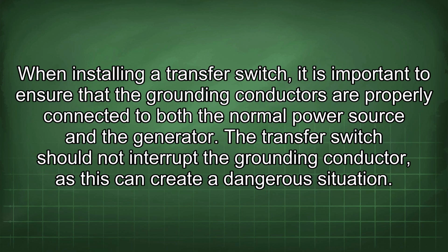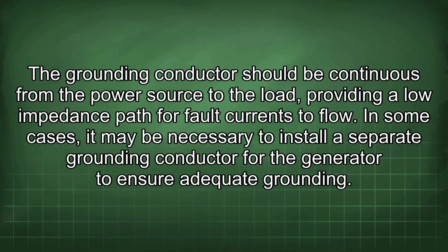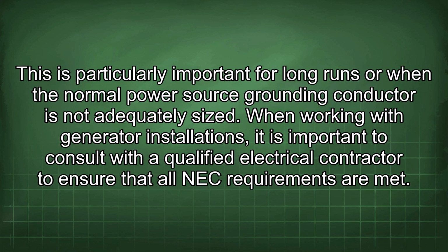When installing a transfer switch, it is important to ensure that the grounding conductors are properly connected to both the normal power source and the generator. The transfer switch should not interrupt the grounding conductor, as this can create a dangerous situation. The grounding conductor should be continuous from the power source to the load, providing a low impedance path for fault currents to flow. In some cases, it may be necessary to install a separate grounding conductor for the generator to ensure adequate grounding. This is particularly important for long runs or when the normal power source grounding conductor is not adequately sized.